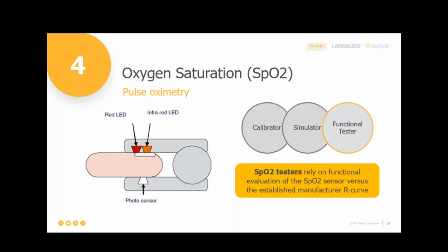I don't want to go to rainbow yet. So the way that the algorithms work is when you're doing design validation and getting your clearance to market from the US FDA, for sure, you have to provide breathe down studies that show healthy volunteers who have agreed to allow themselves to be deprived of oxygen, and then make the measurements and see what happens. So we see the desaturation that happens. The result of that is the raw response curve, or R curve.